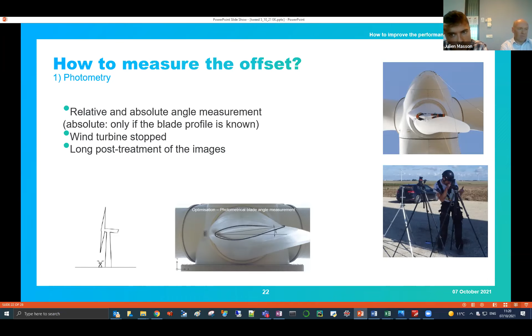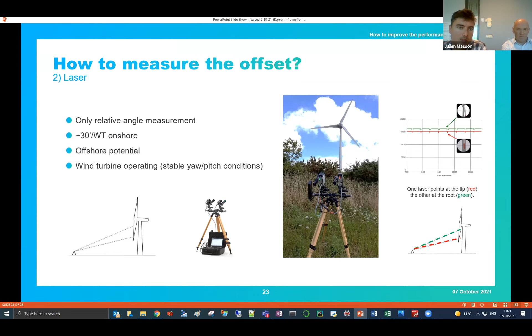The second option is a laser measurement, and it's quite a fast option. You can measure one turbine in about 30 minutes. That's the option we used to measure 84 turbines in France and Belgium. It's quite useful because it's quite fast. You just have to go in front of the turbine, and the turbine is still operating, and the blades are passing through the laser, as you can see here in the lower right image. Then there is the profile. It's not the perfect profile of the blade, but the same profile for the three blades, so you can compare and get a relative difference of angle. In the end, you can retrieve which blade is misaligned compared to the other ones, and apply those offsets to correct the pitch misalignment.